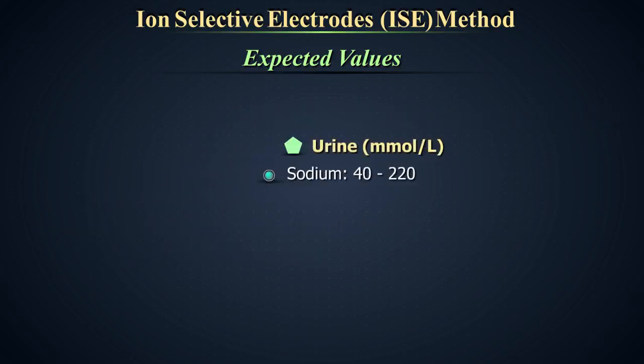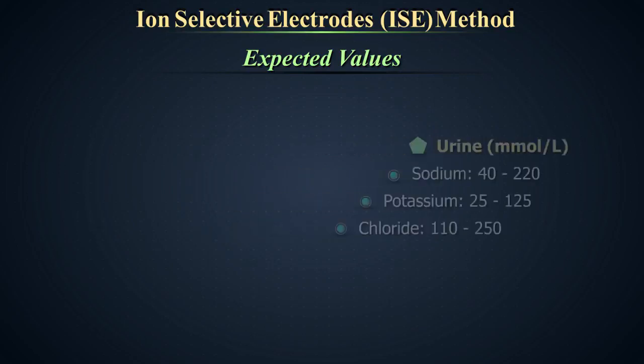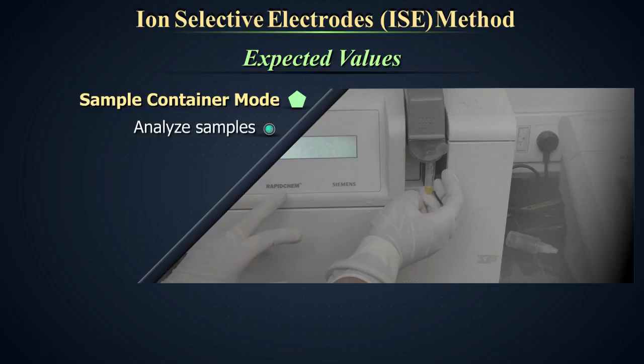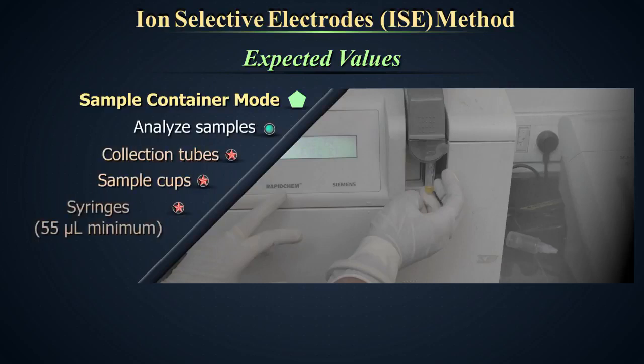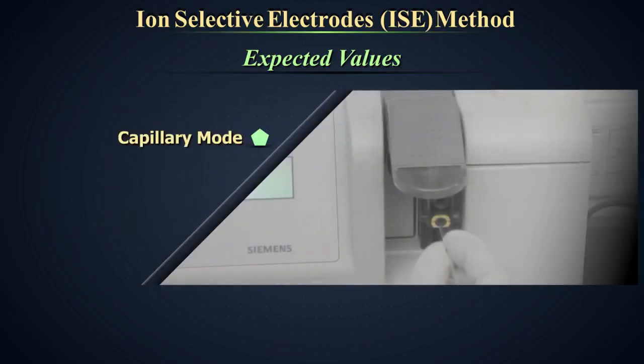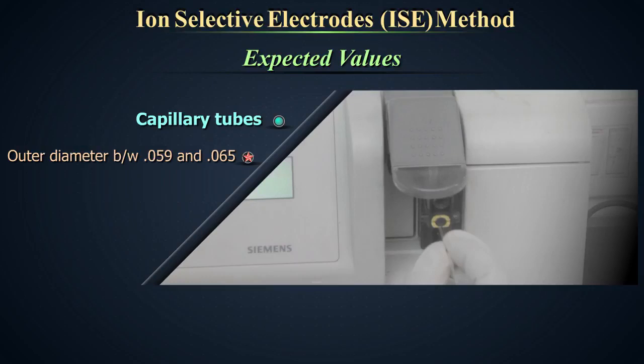Urine, sodium, 40 to 220 millimoles per liter. Potassium, 25 to 125 millimoles per liter. Chloride, 110 to 250 millimoles per liter. In this instrument, samples can be run in two different modes. Sample container mode is to analyze samples from collection tubes, sample cups, or syringes. Capillary mode, to analyze samples from capillary tubes. Capillary tubes must have an outer diameter between 0.059 and 0.065 and a minimum sample capacity of 55 microliters.